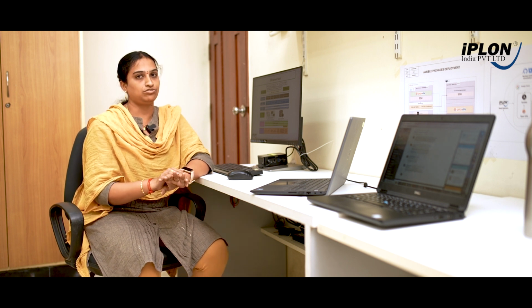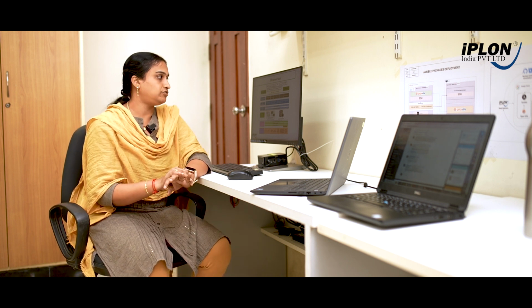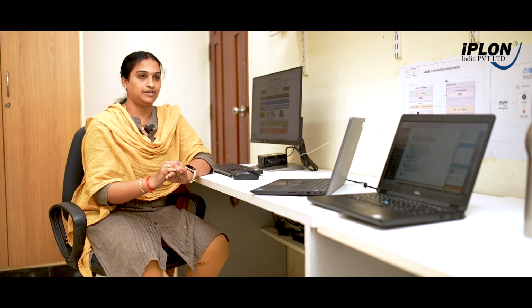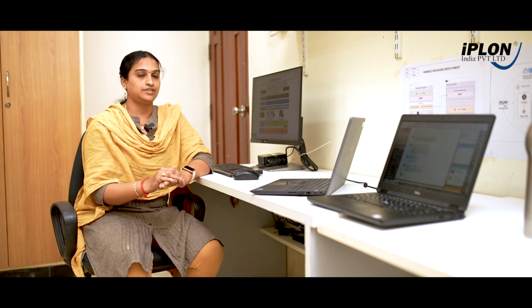And to weather stations also we have to send the data. For that we are using the FTP protocol. And for load dispatch centers also we will be sharing the data. For that we are using the IEC 60870 protocol. And on top of that there will be the cybersecurity, VPN and firewall. VPN is a virtual private network to access the devices remotely. Whenever there is an issue or any support needed by the customer, we can access our devices remotely and give support to them.